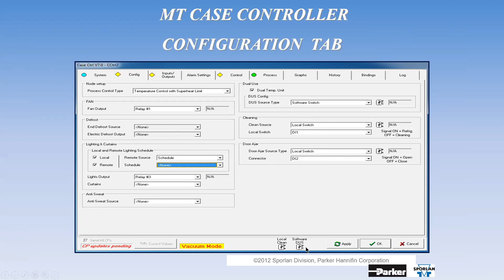Okay, or do I have a software clean switch? The next tab is all my inputs and outputs. Temperature 1, 2, 3, 4. Am I using digital input 1? Am I using digital input 2? My environmental variables, am I using them? Yes or no? Where are they coming from? Guys, slow me down if I'm going too fast. Here's my valve. Here's the drop down.